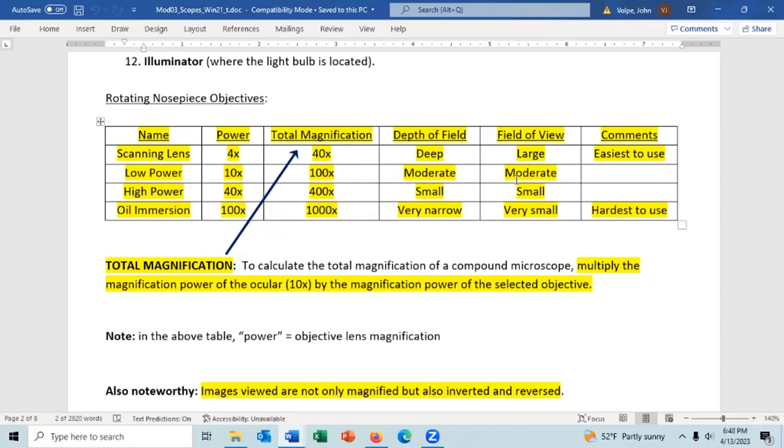And then when you go up in power to the 40x lens, you should shut down the iris diaphragm further because the field of view is shut down further. And you want the cone of light to be about the same size as your field of view. And then for the 100x lens, you have the narrowest field of view. You should shut down the iris diaphragm essentially to about a pinprick because that's the size of your field of view.